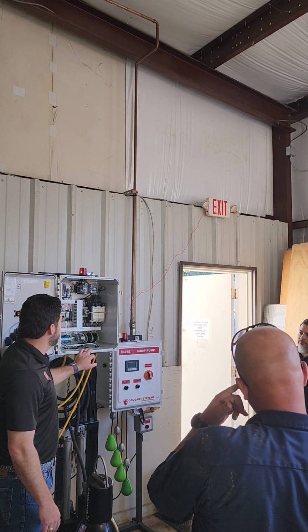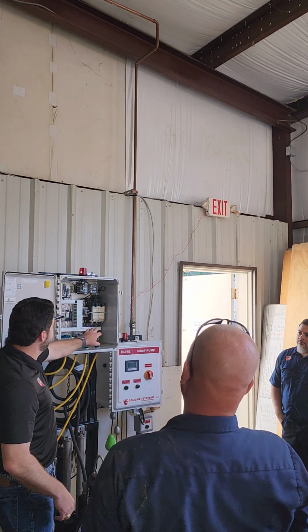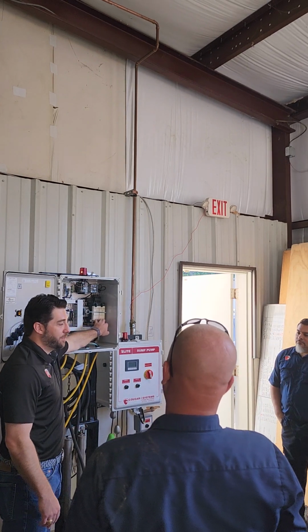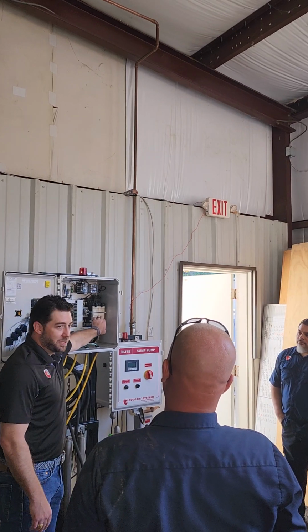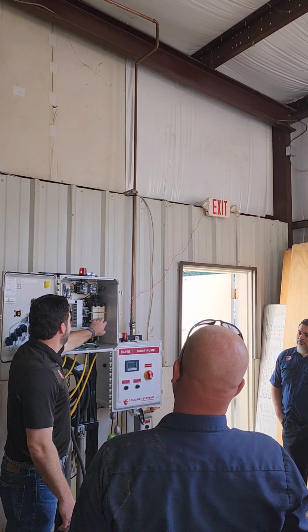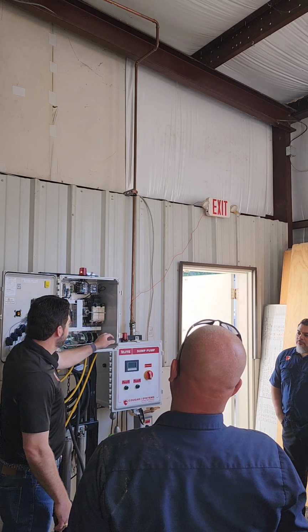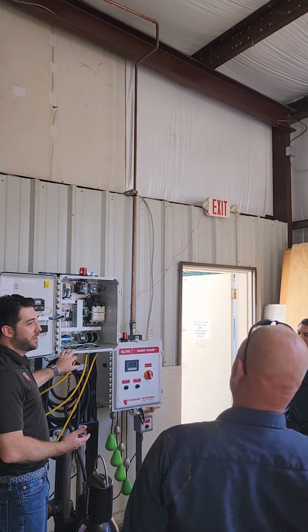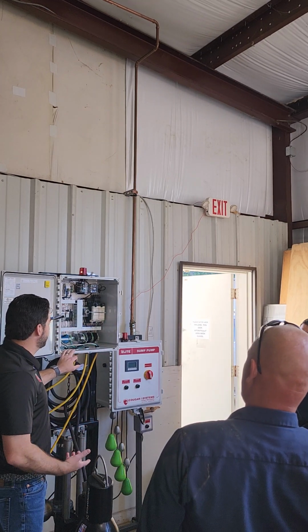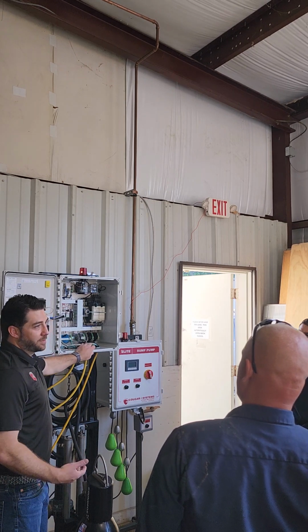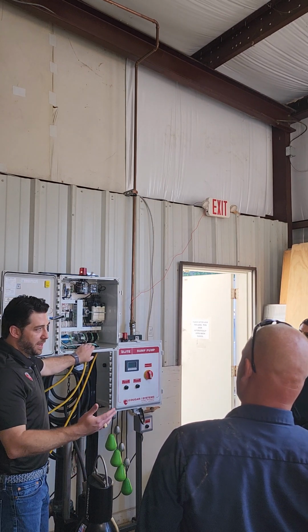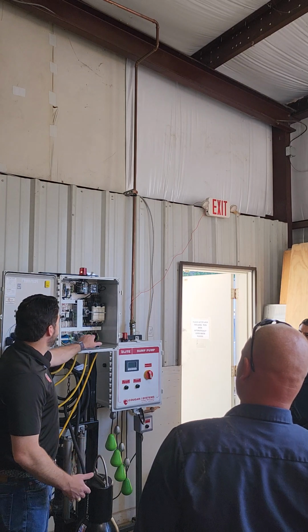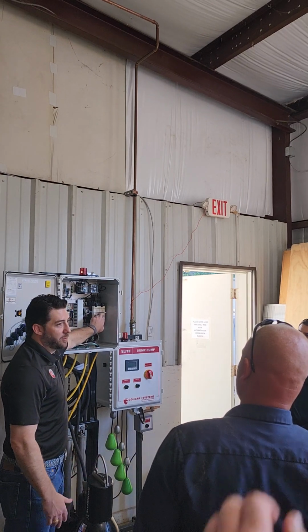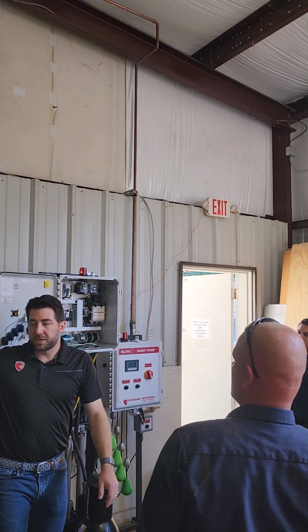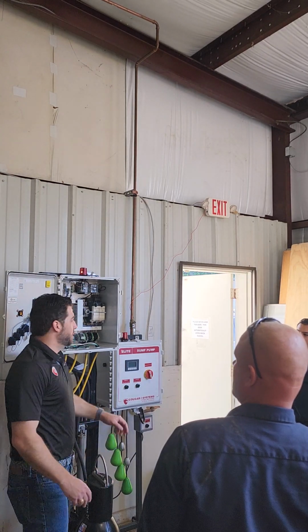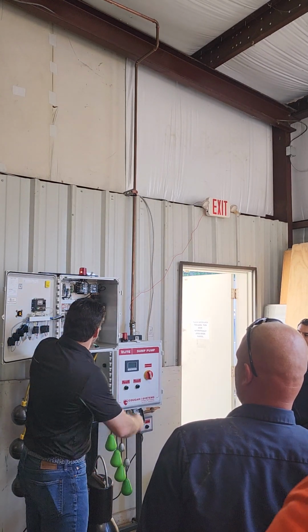The motor circuit's a little bit different. And I think these are back available. We were having some supply chain issues with these, so there were some Elite panels that went out without these. But these are a different style. They're an electronic, not a thermal overload, so they have a wider range. So what that allows us to do is build the panel to handle up to 32 amps, which is up to about a 15 horsepower pump. But it only requires 3 different overload ranges. That's probably 10 plus overload ranges with this style. So if we needed to, we could swap these out.